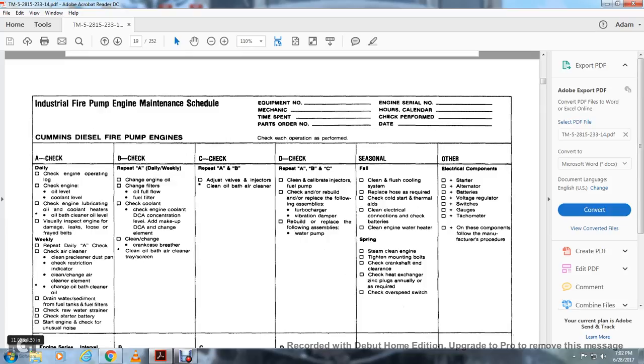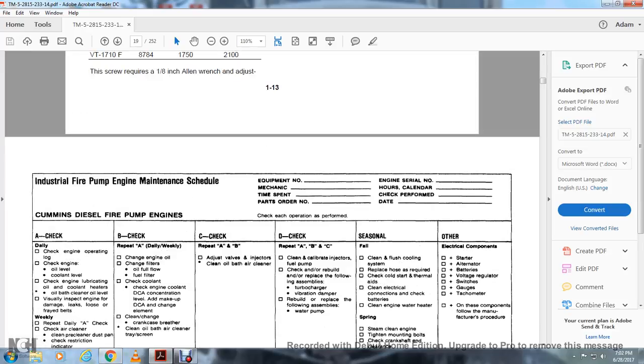Check the raw water strainer. Check the starting battery. Start the engine and check for unusual noises. B, weekly check: repeat daily checks. Change engine oil and change the fuel filters, oil full flow, fuel filter. Check the engine coolant DCA concentration level and add as needed. Make up the DCA and change the element. Clean and change the crankcase breather. Clean the oil bath air cleaner and the tray screen.